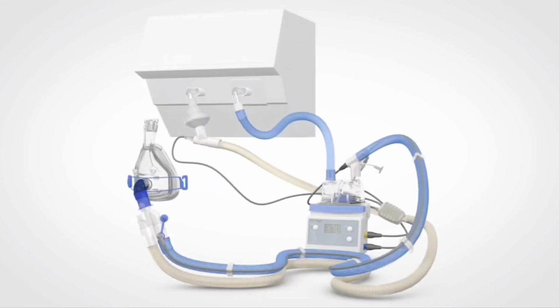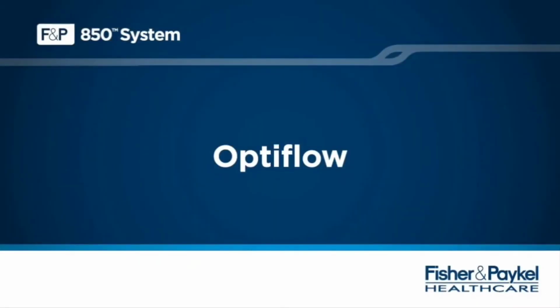For comfort, the humidifier can be adjusted to mask mode by pushing and holding the mode button on the top right of the display and control panel. This mode reduces the temperature of the delivered gas to skin temperature. We have now covered the dual limb ventilator applications of the MR850 system. Finally, let's look at delivering oxygen with the MR850 system.